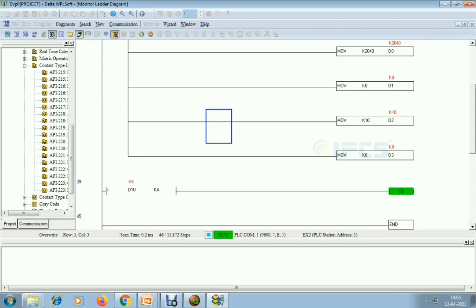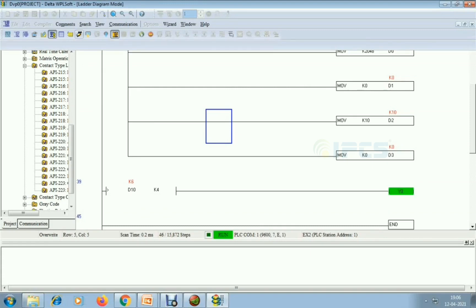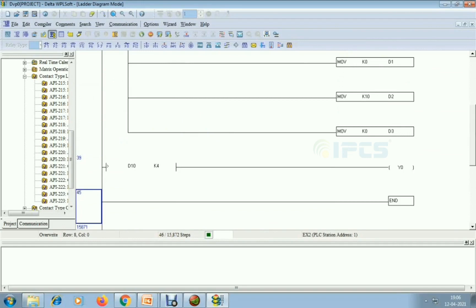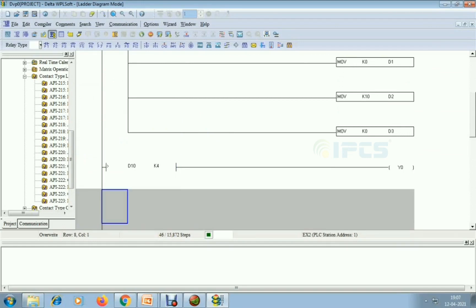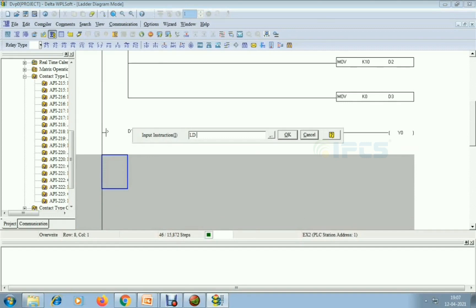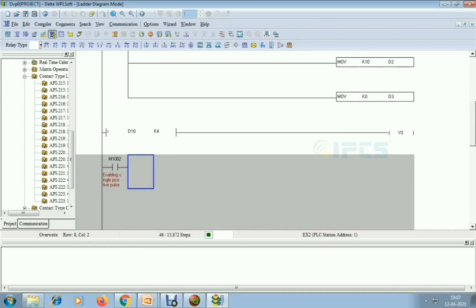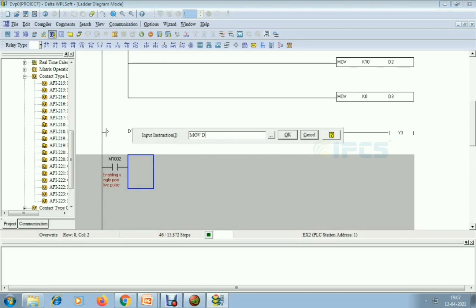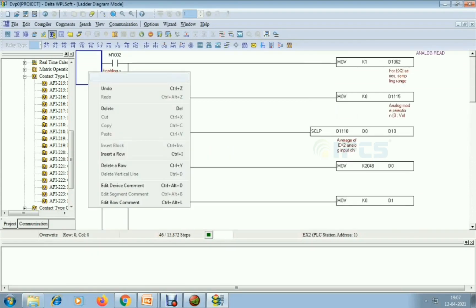Next is analog write mode. I am going to the edit monitor, adding rows with Ctrl+I. I'm giving the contact LD M1002 — this is an enabling pulse, a first positive pulse giving the first scan time. I am using MOV D10 — the scaled value I got — to D1116, which is the first analog channel output.